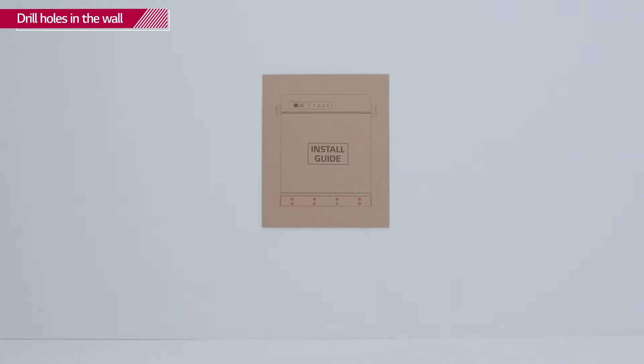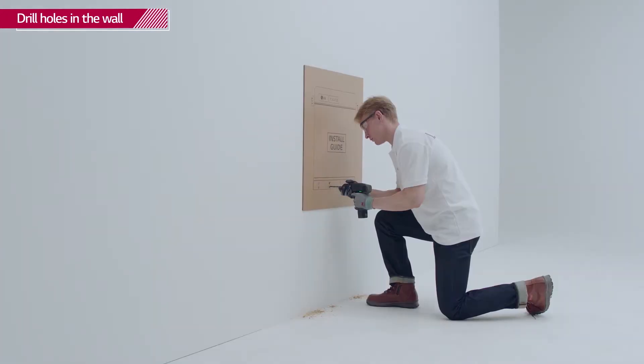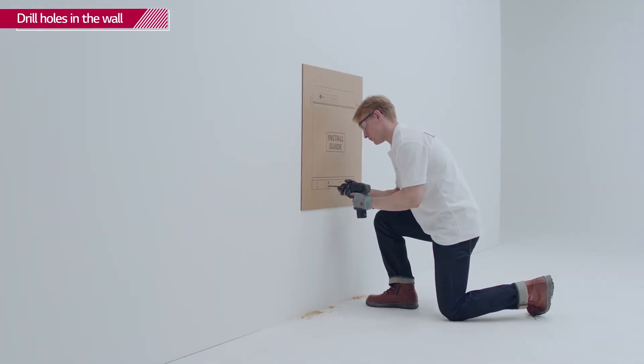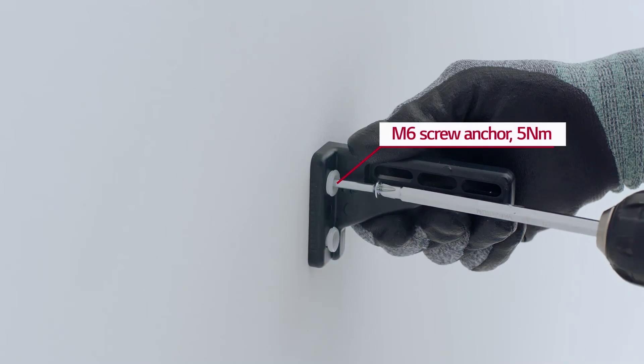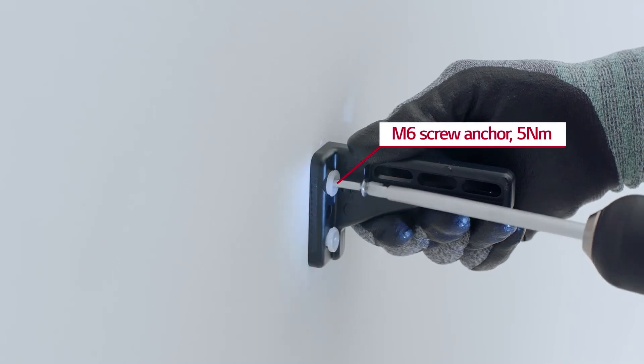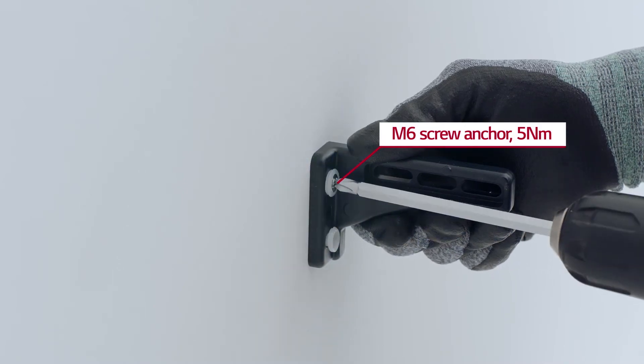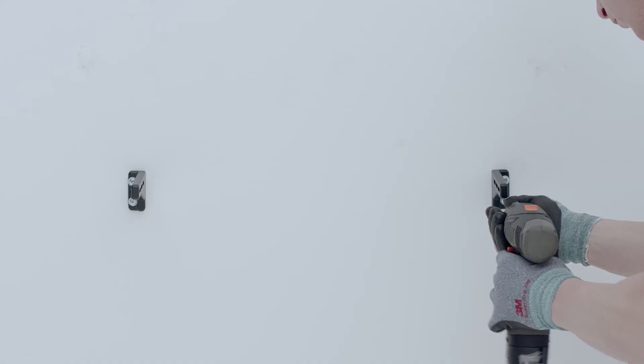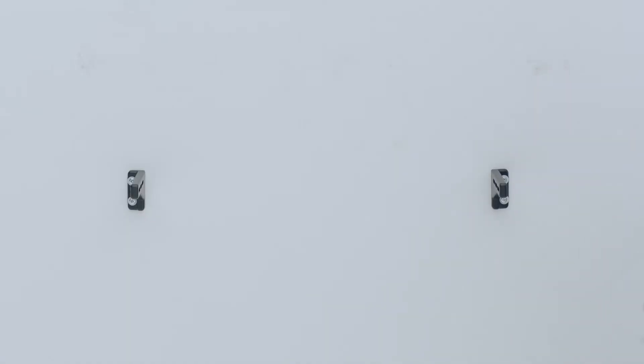Next, drill eight holes in the wall for the M8 screws that fasten the wall mounting bracket. Fix the provided mounting brackets to the wall with the M6 screw anchors with a torque of 5 Nm.